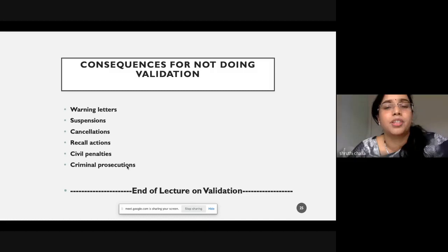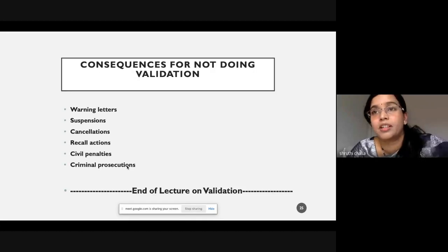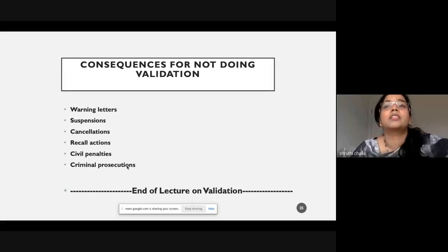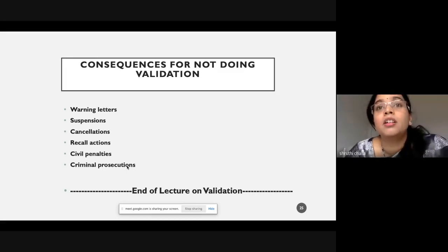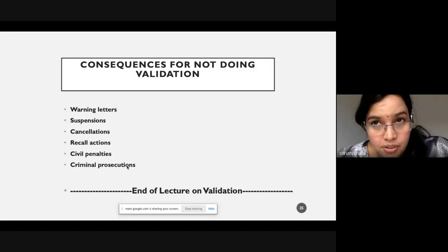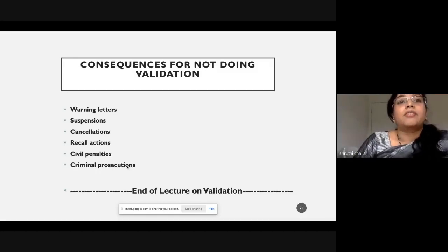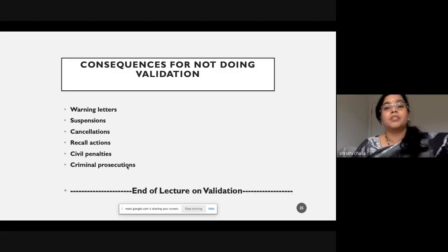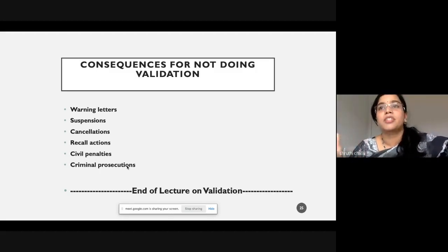So what are the consequences of not doing validation? If the FDA auditors come and find out that we haven't validated a particular process, they will issue a warning letter. If it is a critical piece of equipment or critical process we haven't validated, for example the sterilization chamber, and we are supplying sterile products, they would even suspend the license, and they would ask us to recall the entire product, because we cannot assure, we don't have a high level of confidence, that all the sterile products we placed into the market are sterile. We would have done the quality control test, taken a couple of samples and done a sterility test on them, but that's not sufficient.